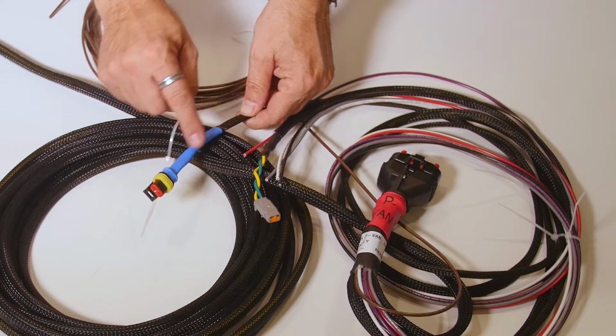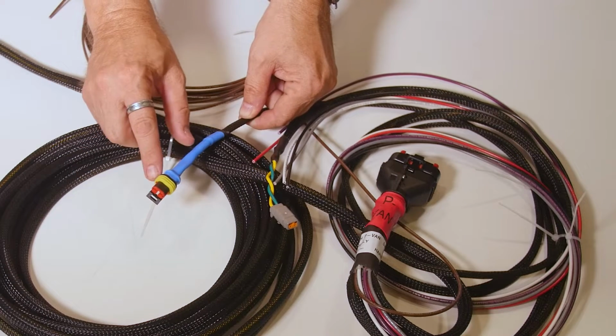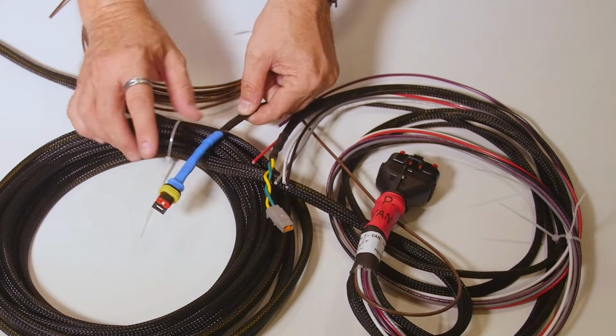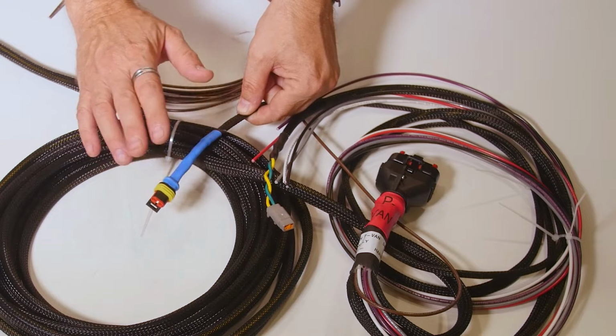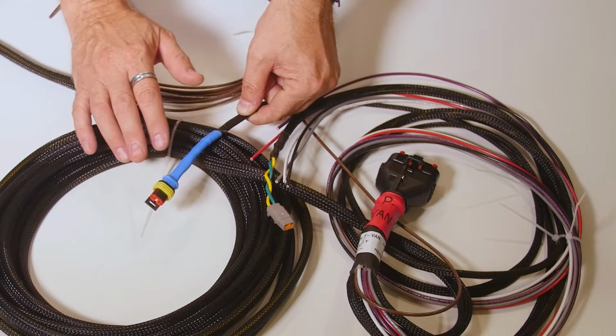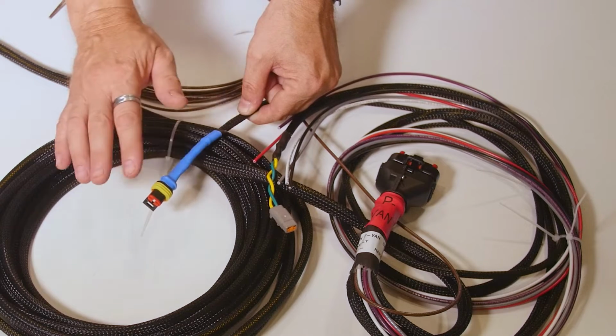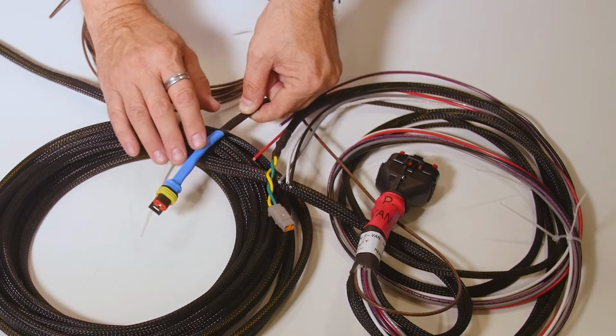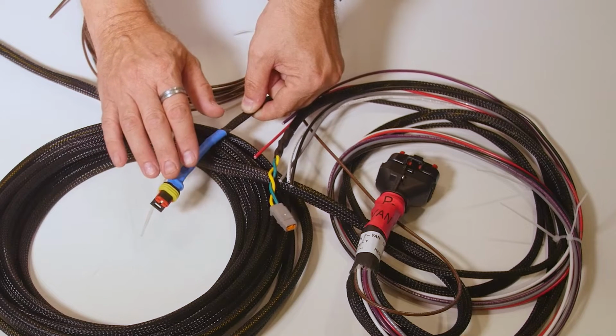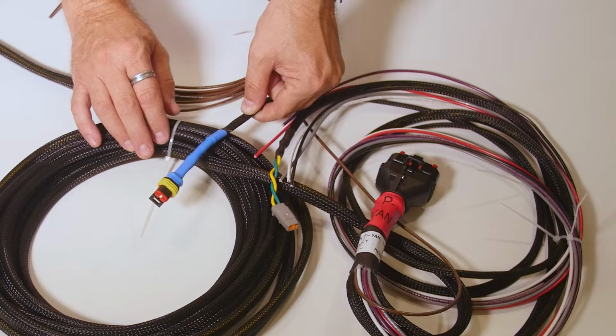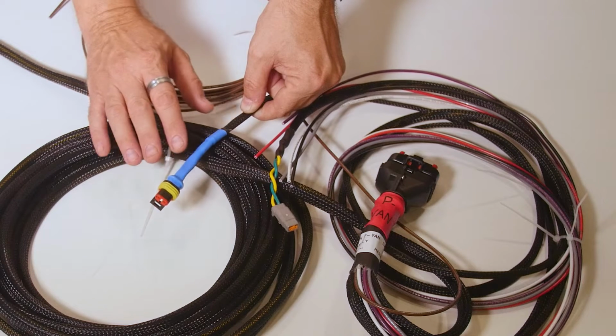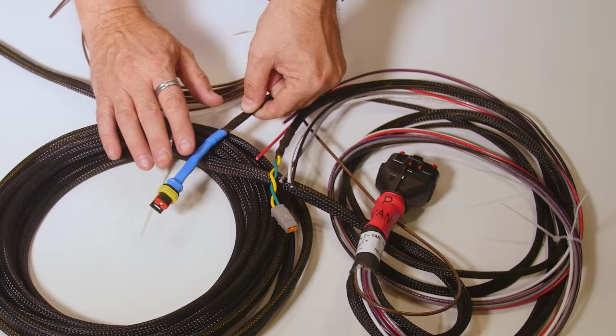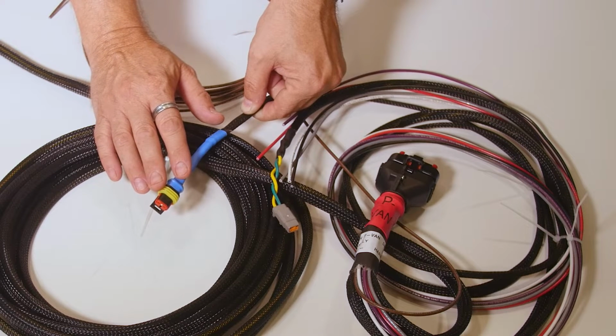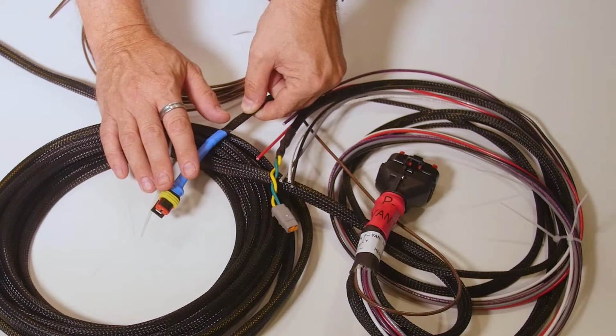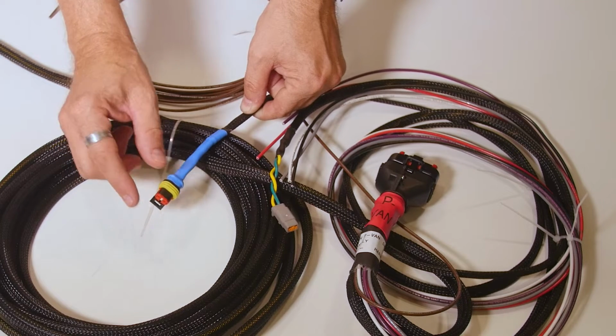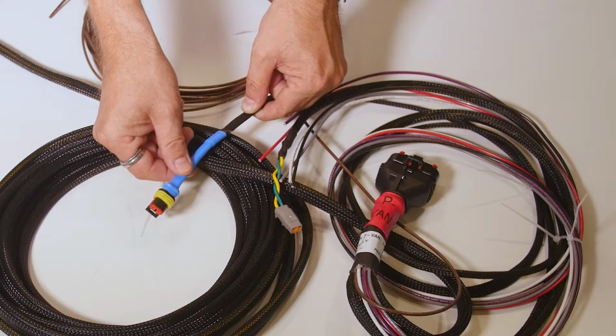This blue heat shrink connector would be for a battery temperature sensor. We highly recommend using CAN-enabled batteries that communicate through their BMS with the rest of your system. Typically the temperature of the batteries is communicated over that CAN data network, so this isn't used. If you're using a legacy battery, say a lithium battery with an internal BMS that has no data communication, you'd want another temperature sensor here that connects to the positive terminal of your battery.